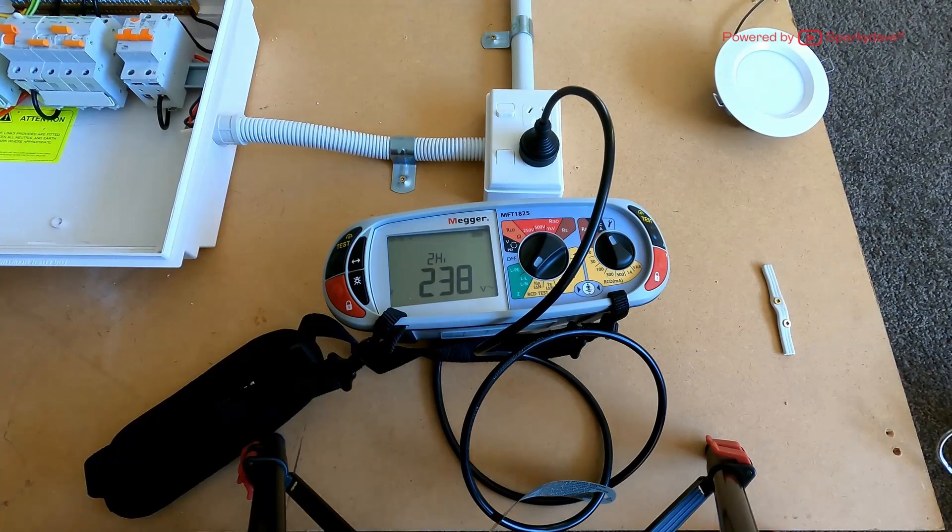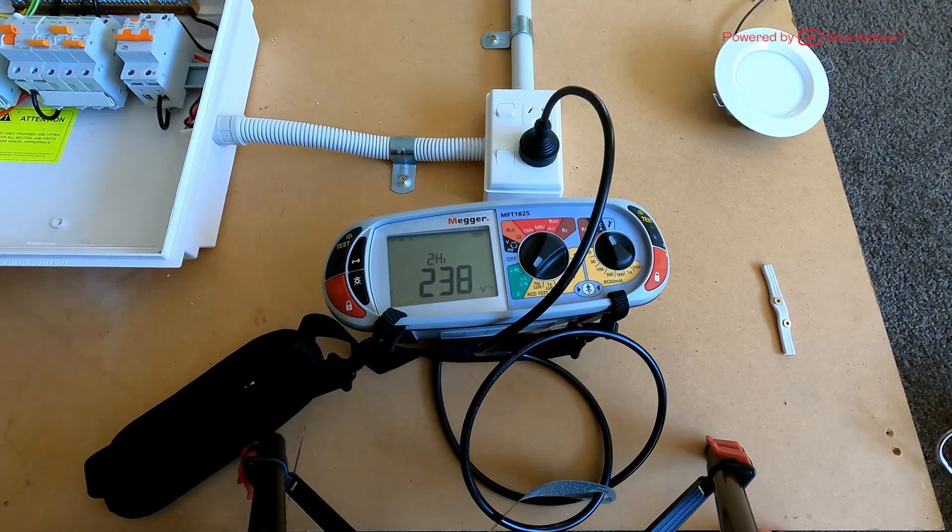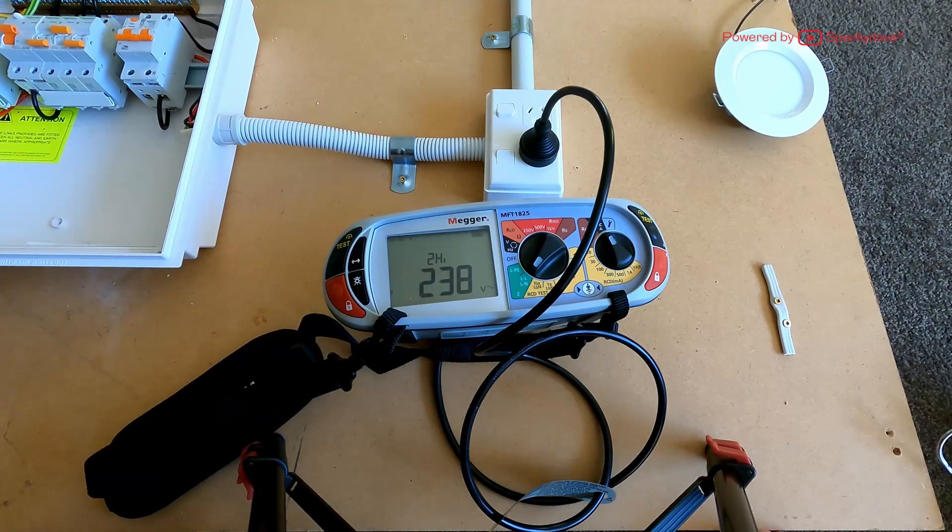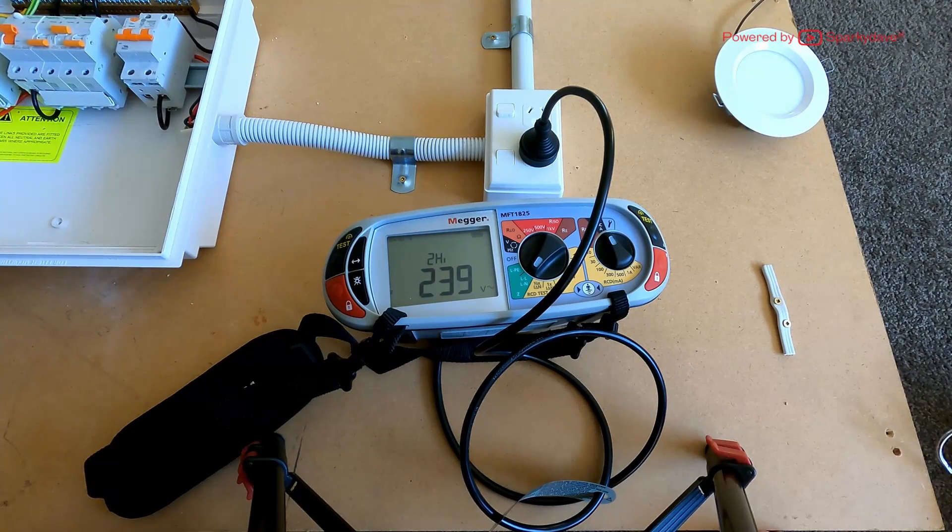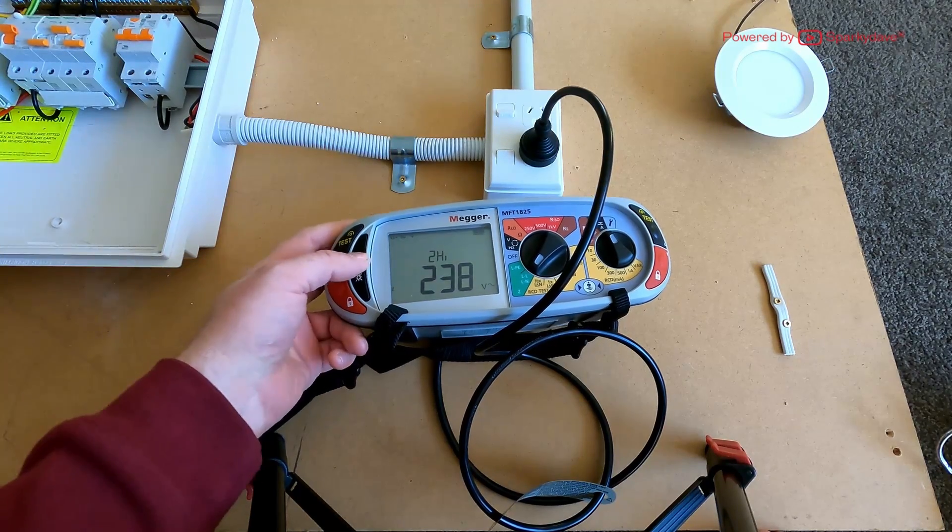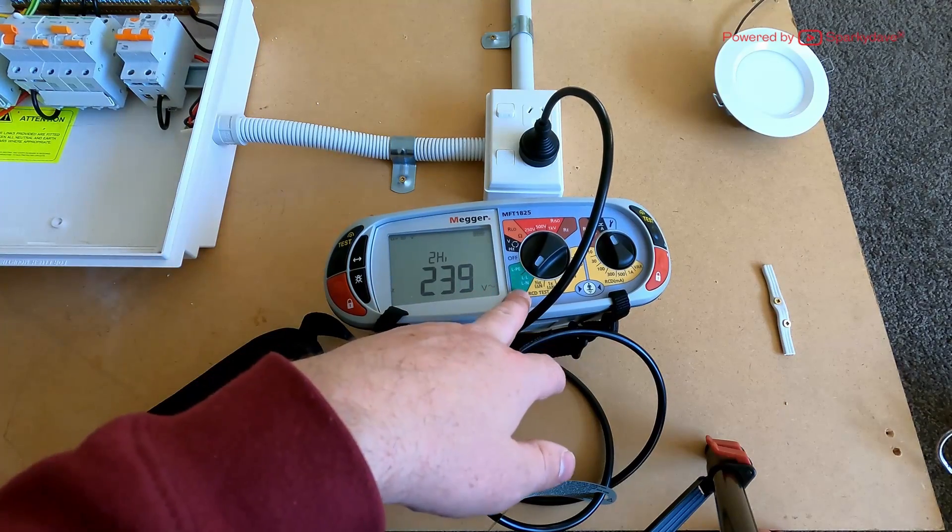Then we put it on line to neutral. Now line to neutral test is always your two lead high current test, because it's the most accurate and fastest test you'll be able to do. You can't change it. The high current test on the neutral is not going to trip your RCD. 1.05 ohms.